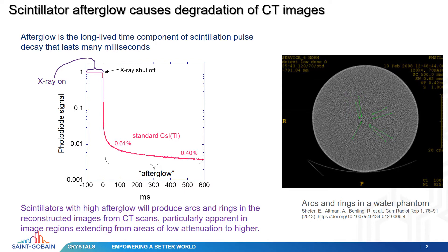Going down slowly to 0.4% at 500 milliseconds. This extra light can produce arc and ring artifacts in the reconstructed images of CT scans. These artifacts are particularly apparent in image regions extending from areas of low attenuation to high. The photo on the right shows an example of arc and ring artifacts in a water phantom, taken from the reference listed there.